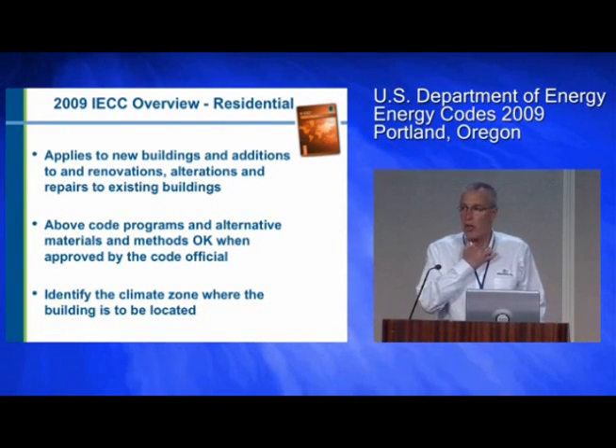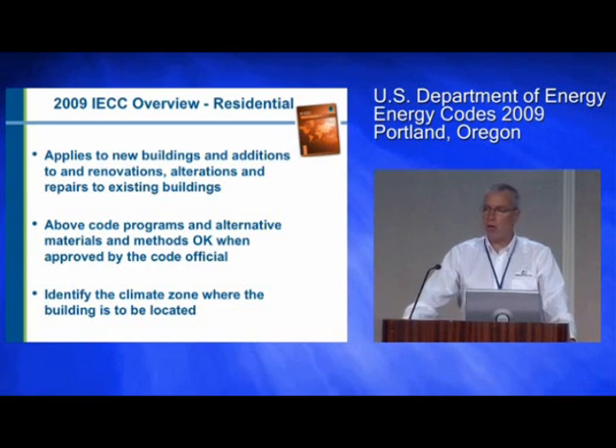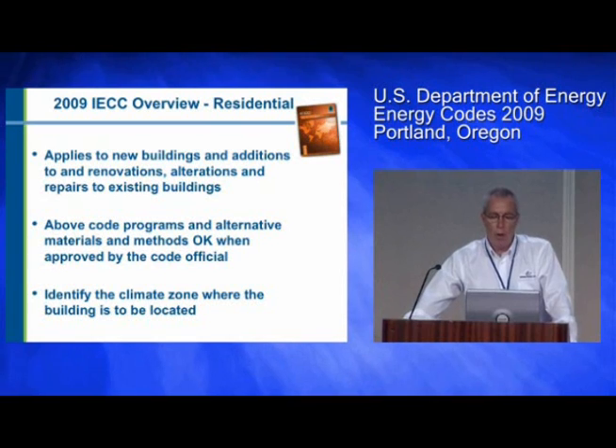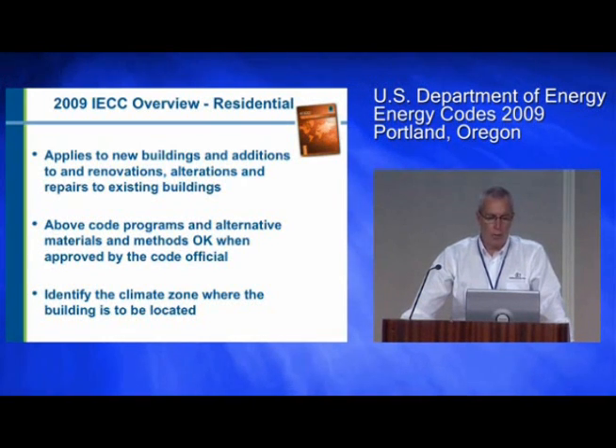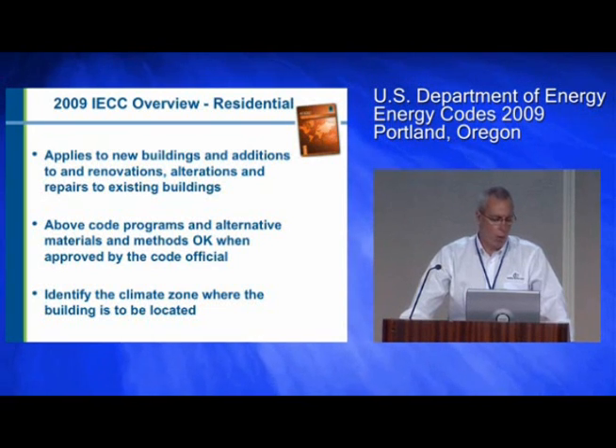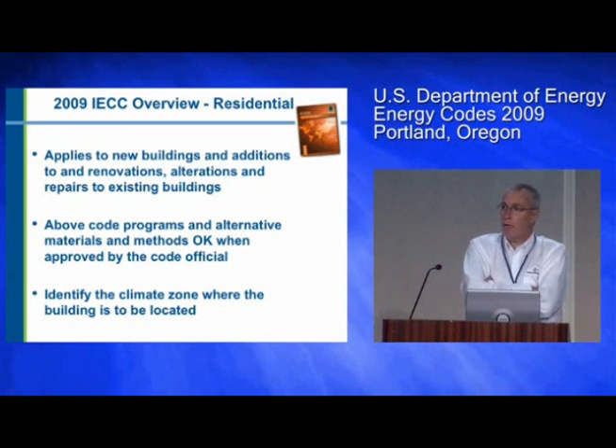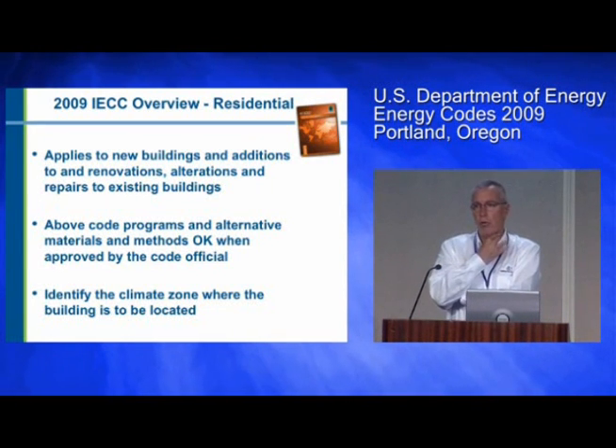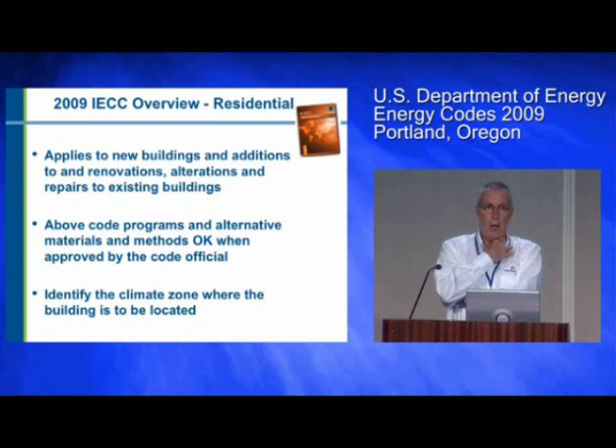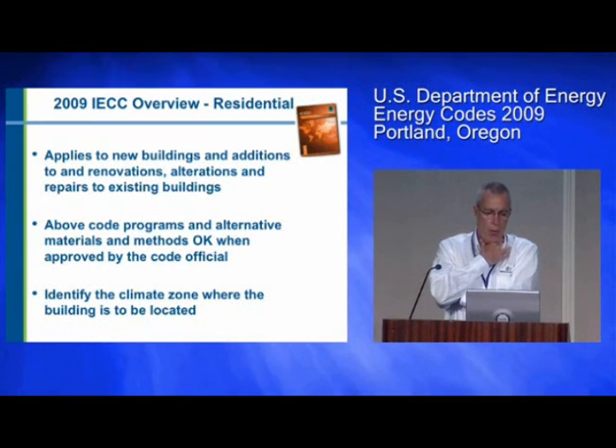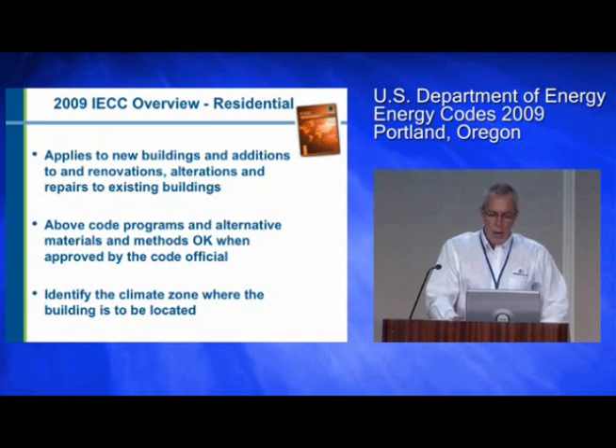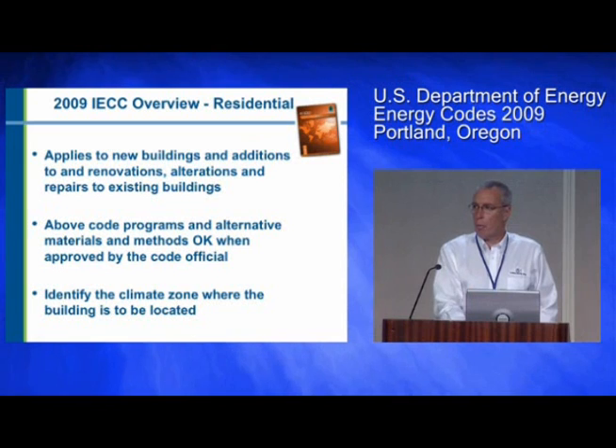So in terms of the IECC, the 09 applies to new buildings and additions. This is a high-level overview, renovations, alterations, and repairs to existing buildings. Above-code programs are okay, and alternate materials are okay when approved by the code official. So if you've got something you want to do that's not specifically covered in the code, you can get building regulatory approval for that alternative. Also, if you have in your state an alternate program, maybe a HERS or something of that nature, you can get a code official to validate that it is equivalent, so you can follow that program instead of the code. And then the code identifies the climate zone where the building is to be located.